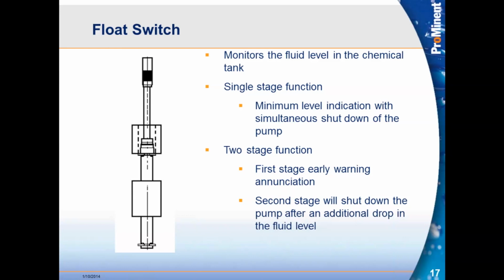The intention there would be we want it to reach the bottom stage, the tank empty stage, and it stops the pump before that level gets below the foot valve. That way it stops the pump from losing prime. So we suspend that slightly higher, and that can trigger the relay output on the pump. So now we can know about it being empty or being to the point where it has stopped the pump.